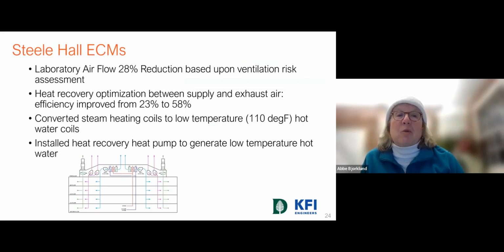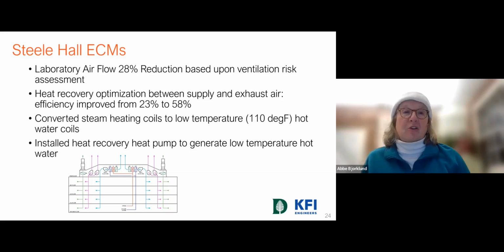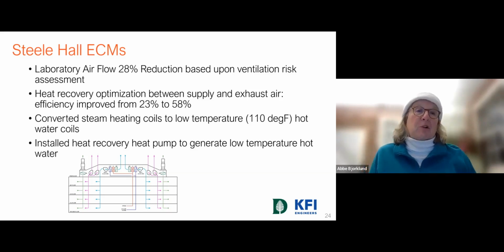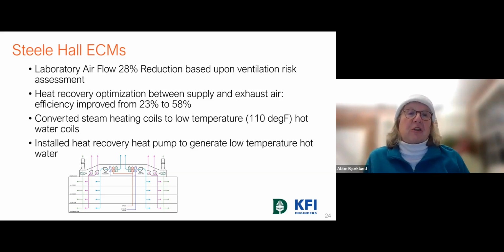So the ECMs that we ended up installing, the big one was a ventilation risk assessment. You're probably familiar with Steele Hall. It's a chemistry building with very large ventilation, a lot of 100% outdoor air systems. So we did a risk assessment to figure out if there were opportunities to reduce airflow in some of those labs, but still maintain safety for the students and professors using those spaces. And that resulted in a 28% airflow reduction.